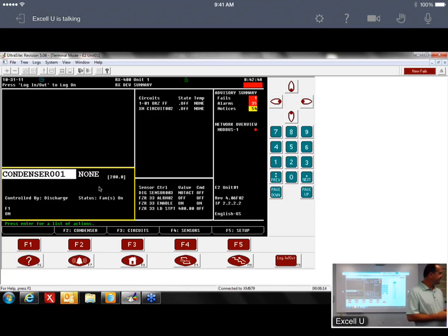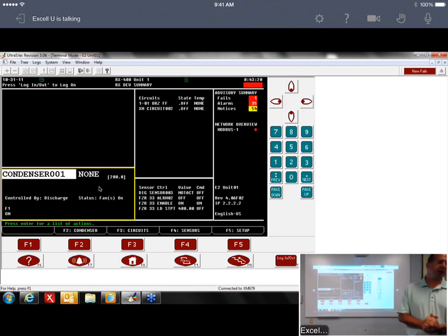One of the things for you guys is it actually helps reduce your startup time too, because now you're not setting superheat on 70, 80 cases in a store at startup. This thing controls your superheat. I've had guys tell me that'll cut 3 or 4 days off your startup. It also helps with serviceability, you're not always having to check superheat and things like that, so it pretty much takes that out of the mix. That's something I think will help you guys out.